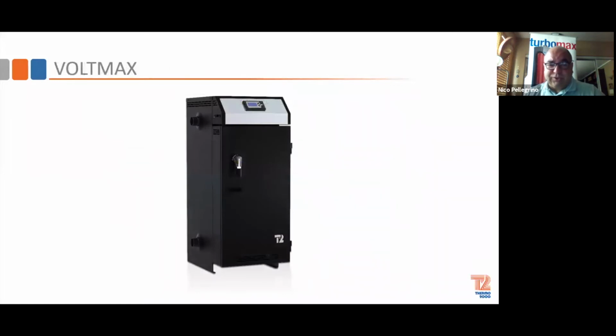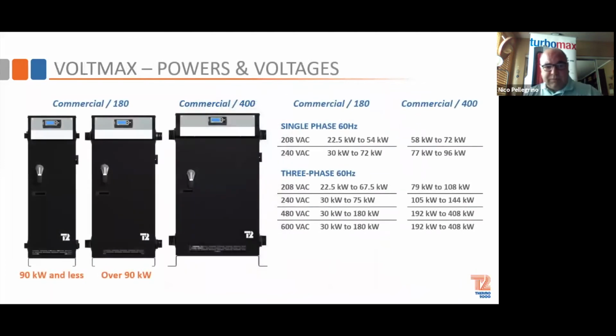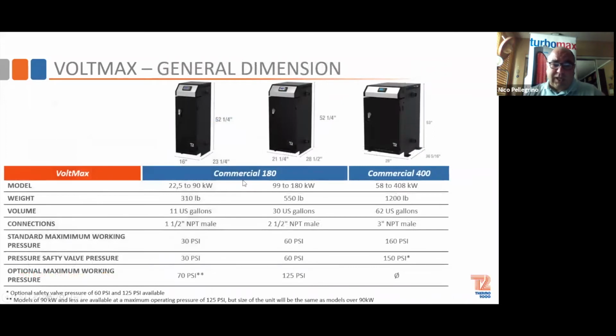So we get into the Voltmax, which is our commercial boiler. It comes in 3 different sizes as far as case goes. 90 kilowatts and less is this framework. Over 90 kW is this. And then we get into our very big commercial. That box never changes, just the kilowatts change in the box. Again, many phases, many voltages, three-phase, single phase. Just like our small Minis and Ultras, it's in and out. You don't need primary-secondary. Not saying you can't, but it does not need it because we're not a heat exchanger. We are a tank and vessel. As you can see, the sizes are 11 gallons, 30 gallons, and 62 gallons.